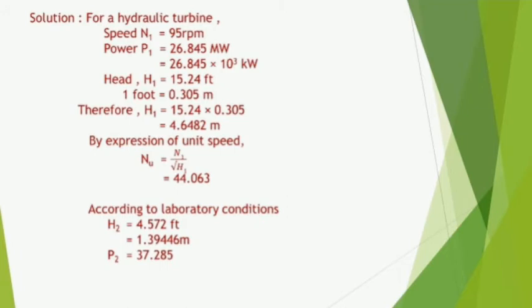For the hydraulic turbine: speed n1 = 95 rpm, power p1 = 26.845 megawatt = 26.845 × 10³ kilowatt, head h1 = 15.24 feet. Since one foot = 0.305 meter, h1 = 15.24 × 0.305 = 4.6482 meter. Using the expression for unit speed: nu = n1 / √h1, we get nu = 44.063.